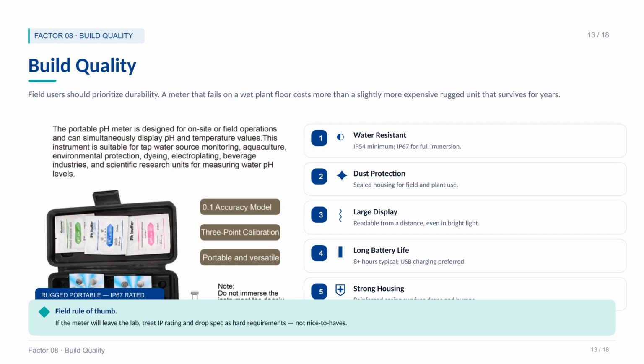Factor 8. Build quality. If the meter will ever leave the lab, treat IP rating and drop spec as hard requirements, not nice-to-haves. Water resistance, dust protection, large readable display, long battery life, strong housing. These are the things that decide whether your meter survives year 3. A meter that fails on a wet plant floor costs you far more in downtime than a slightly more expensive rugged unit that survives for years. Plan for the worst day your meter will ever have.